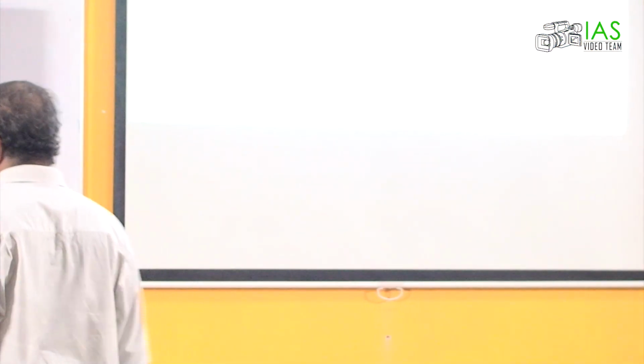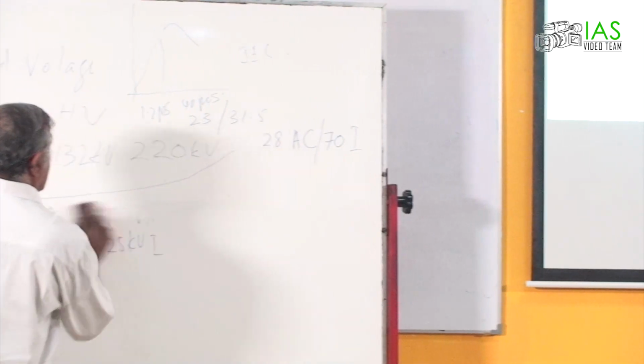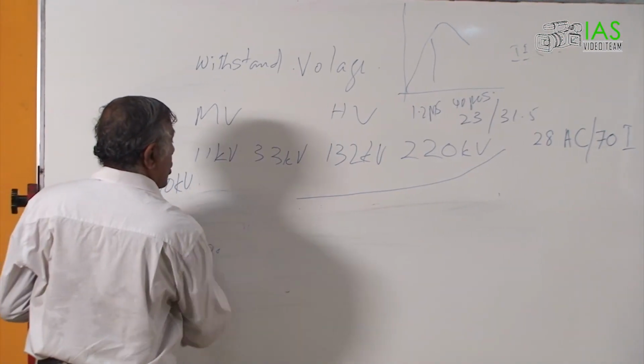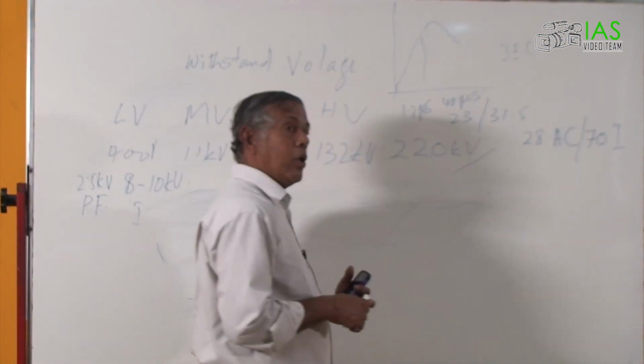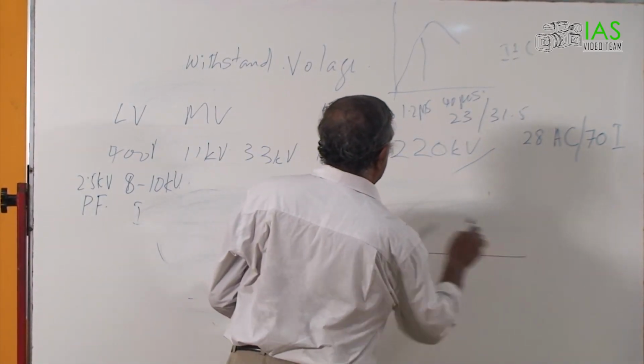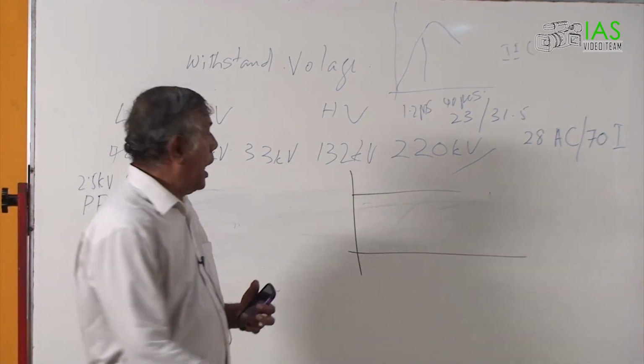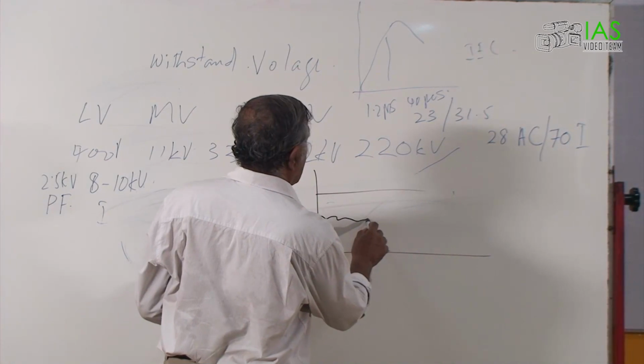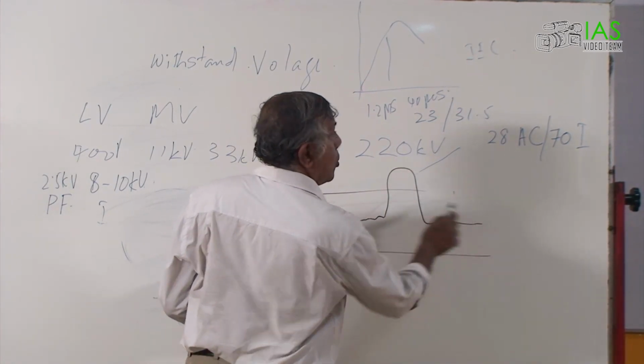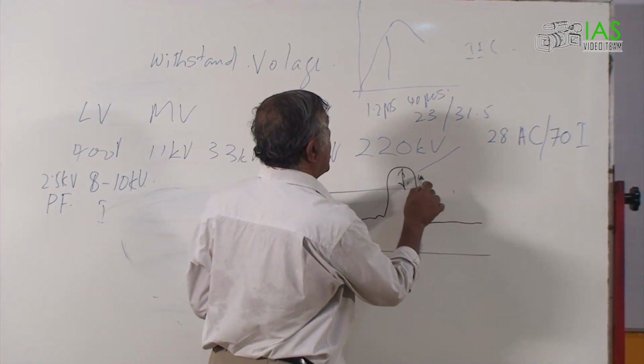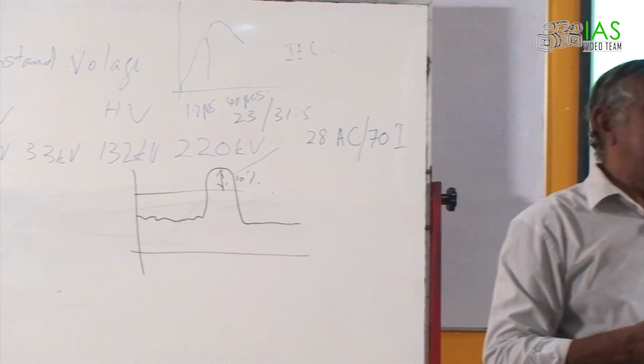So normally it's said, in situations, if your load is 2/3 of the maximum capacity, for the rest of the day you can overload by 10%. So say this is the loading capacity, and if you are running at 2/3 for the rest of the day, for 1 hour, you can overload this by 10%. So with guides like this, if your hotspot temperature is not going higher than 118 degrees, then you can overload that, right?